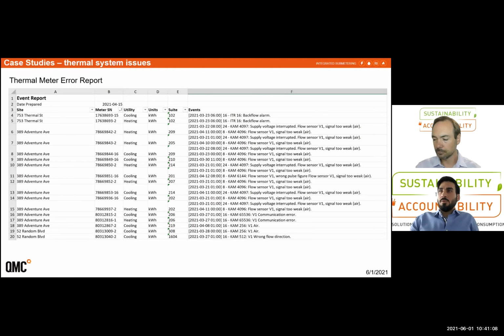Also, one of the other common issues within the hydronic loops is entrained air bubbles, which cause erroneous readings from the ultrasonic type flow meters and thermal meters. And this is one of the other things that could be extracted from the meters within the error logs, alongside supply and return temperature, flow, energy and demand. And this needs to be addressed. We typically notify the building operators that there is excess air within the loop, and they need to rectify the issue. Next slide, please.